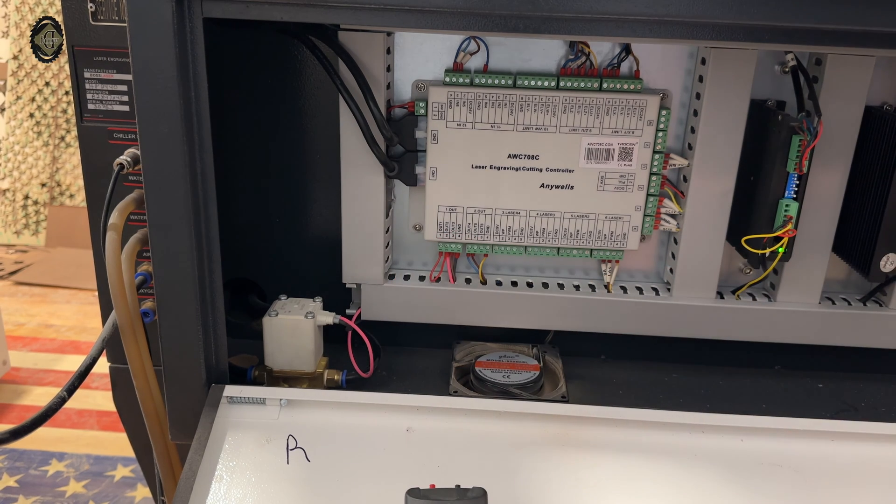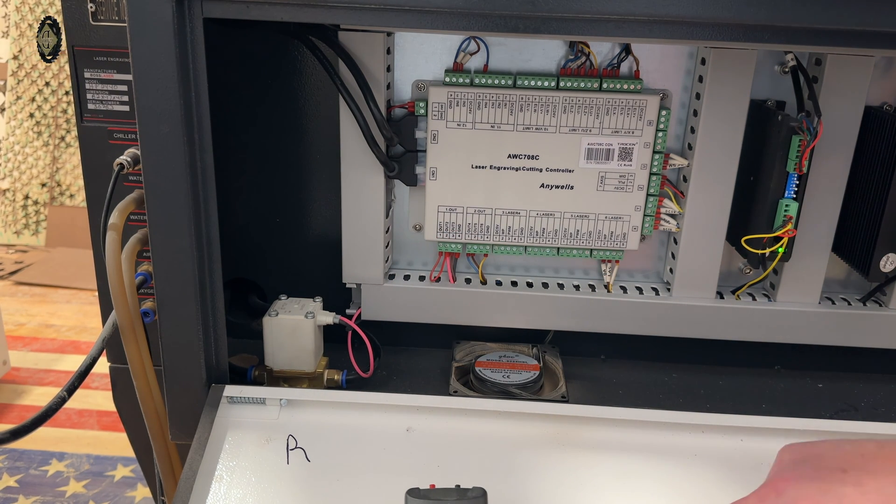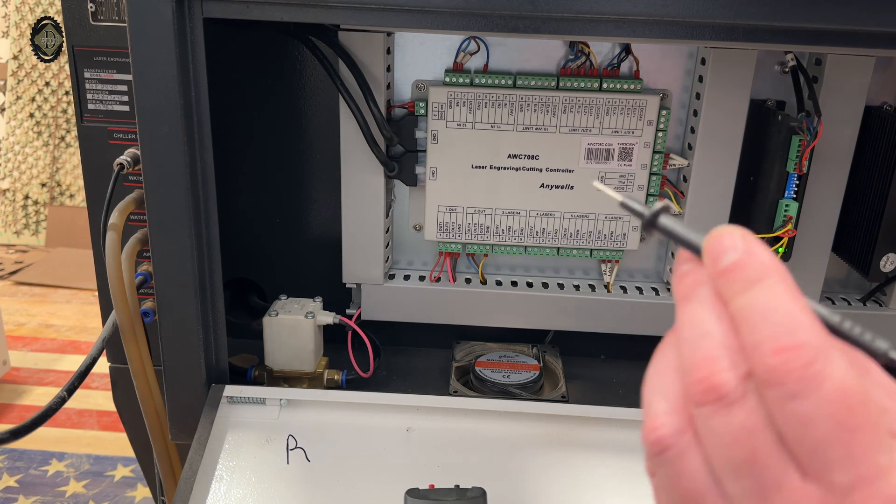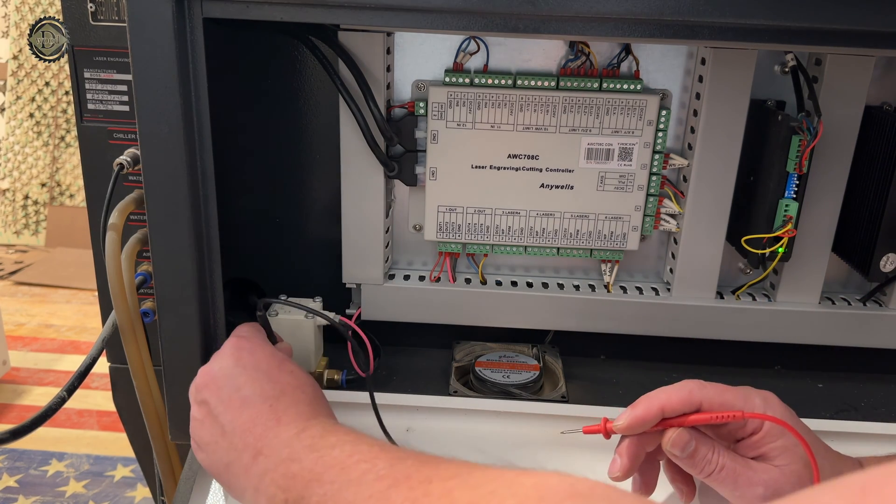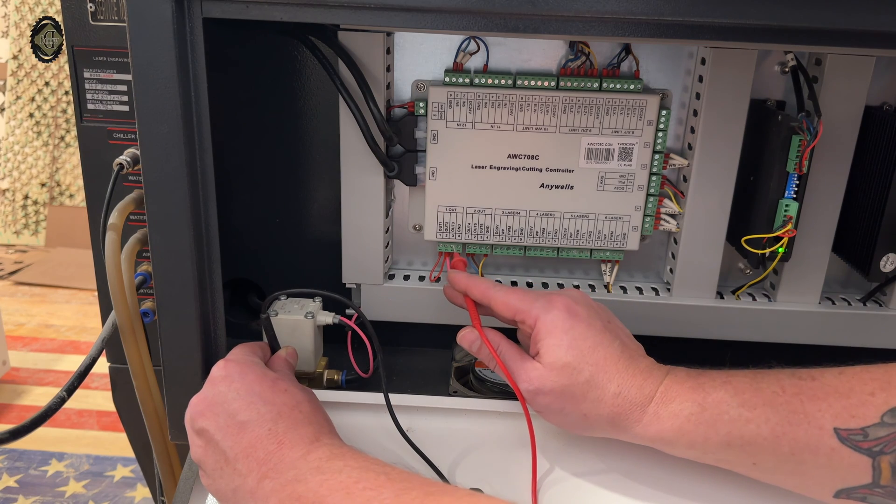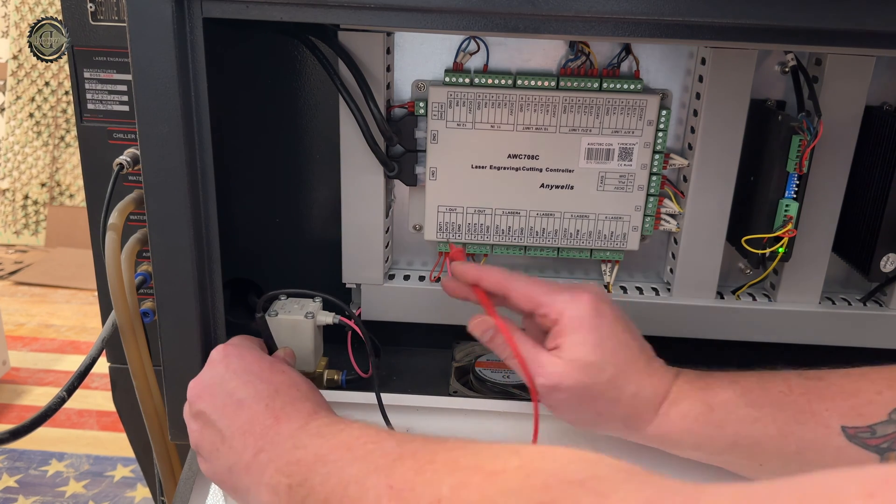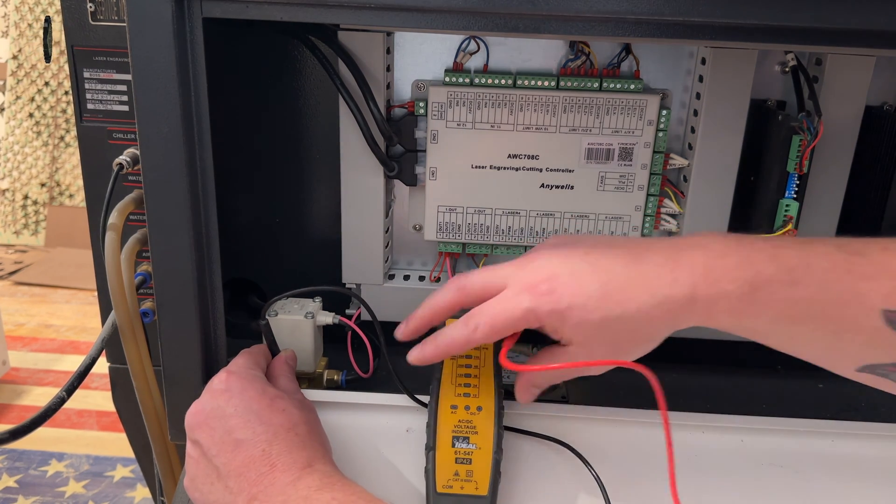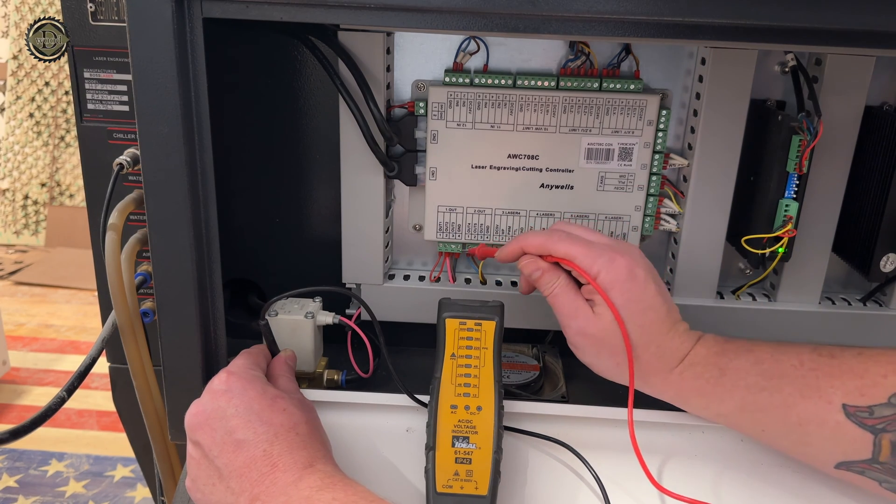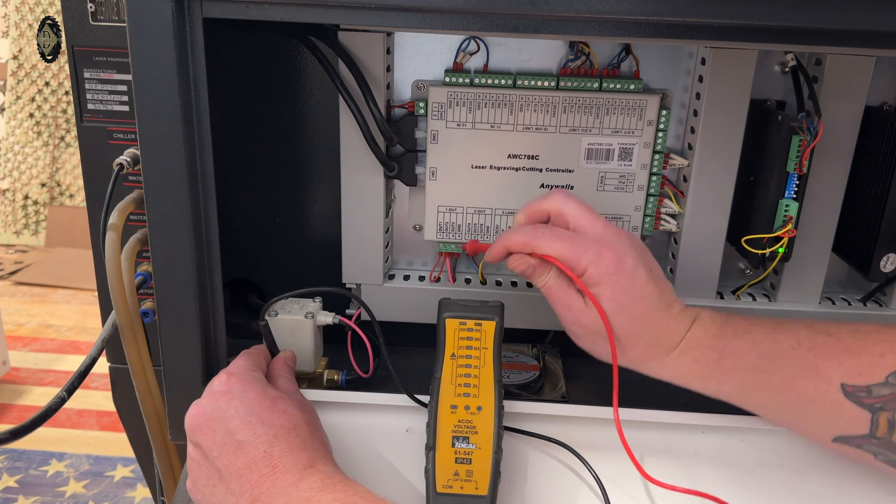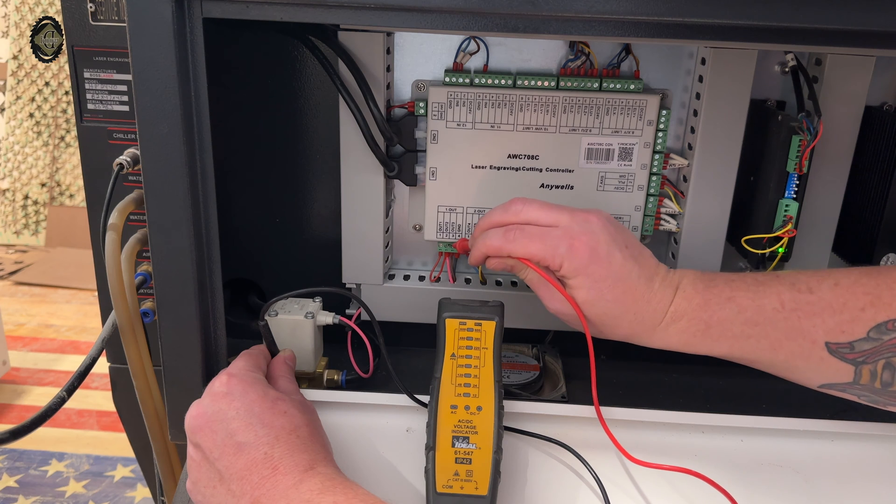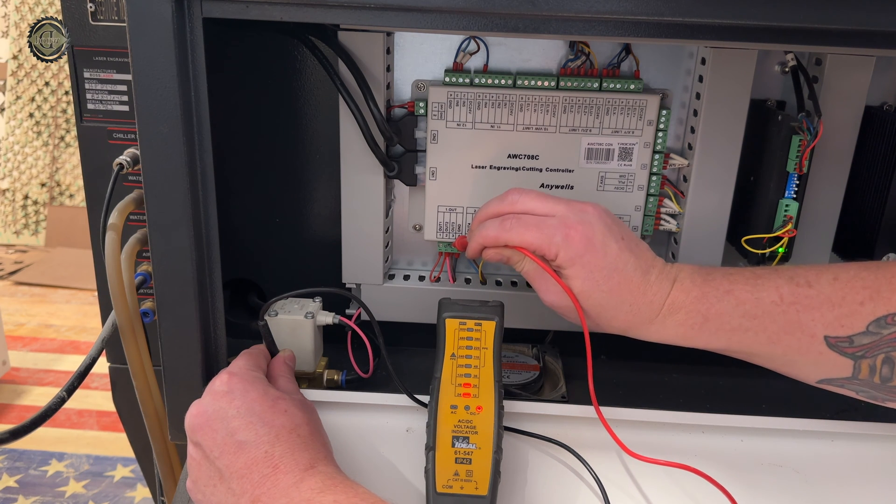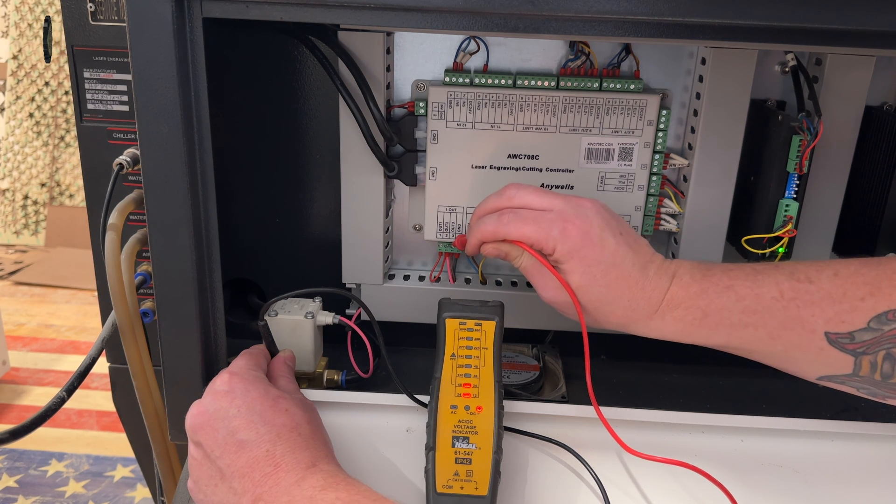What we're going to do to make sure that's the case is take our ground, put it on the ground right here at the motor, and test the connection here at the pink terminal. You can see the lights come on, which shows that we have 24 volts at that point.